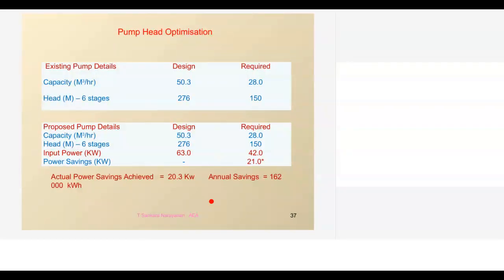See, this is a case that was done for head optimization. During the audit, these details were collected: what is the capacity of the pump in meter cube per hour, how many stages are there, and what is the design head for the pump. So this is what the pump is designed for. The operation is requiring only 28 meter cube per hour. Head requirement also is lower. So now in this case, I have to do throttling for flow reduction. Head control will be difficult because it is a 6-stage pump. I may not be able to reduce the head. Flow I can reduce by throttling.